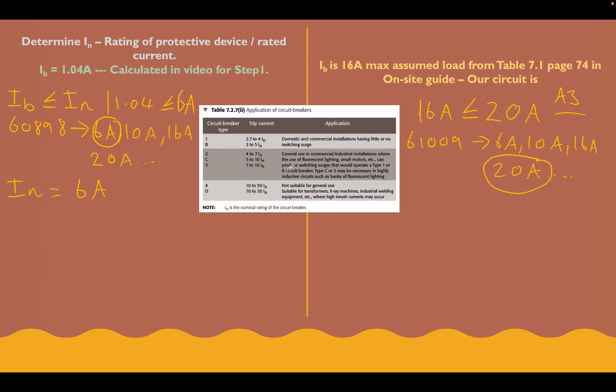Let's now look at these tables in the middle and keep this quite brief. Let's look at it and try and work it out. Circuit breaker type in this column, the trip current. So this is where these particular circuit breakers will trip, and then the application of them. Let's look at a type B here. We're saying it's for a domestic and commercial installation having little or no switching surge. Let's look at a C type here. General use in commercial industrial installations where the use of fluorescent light in small motors can produce switching surges that would operate a type 1 or B circuit breaker.